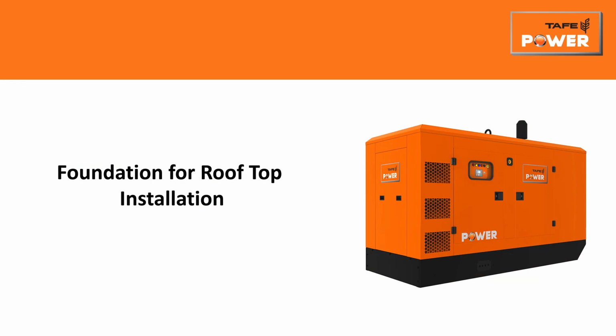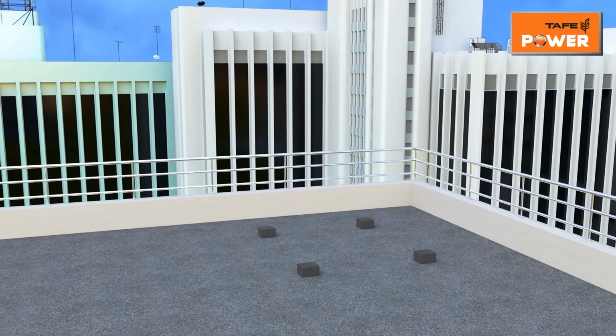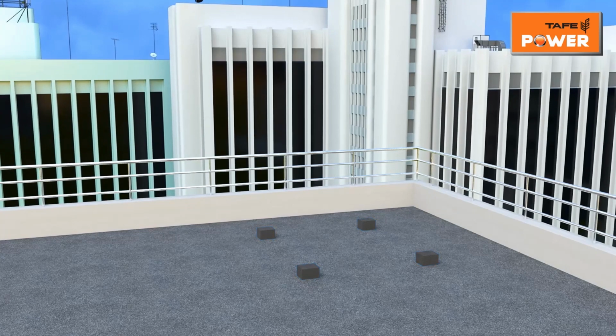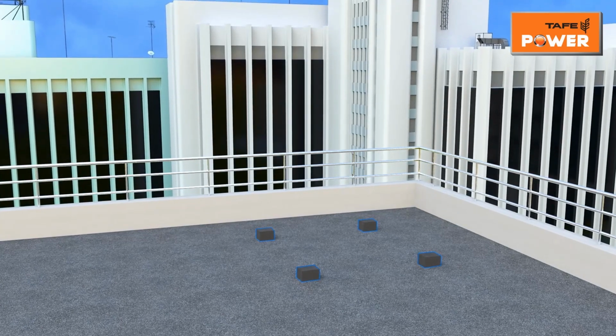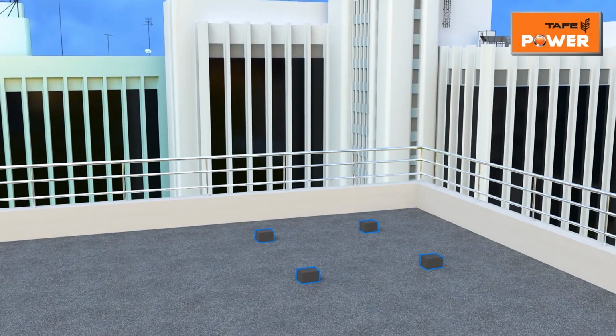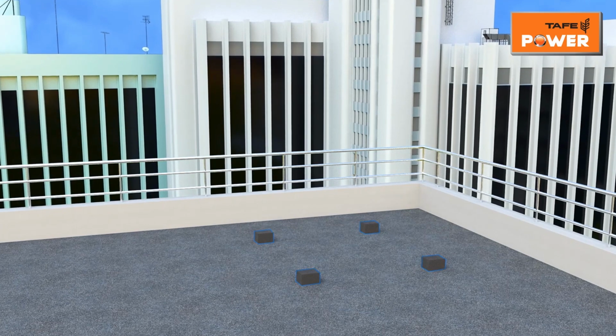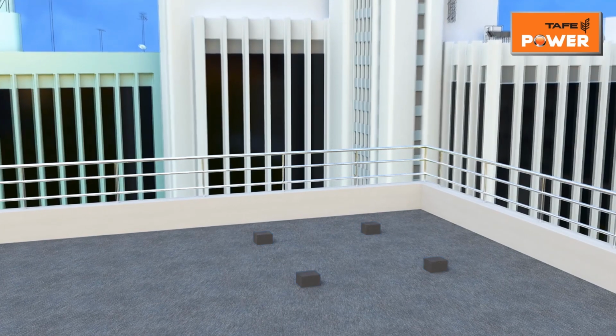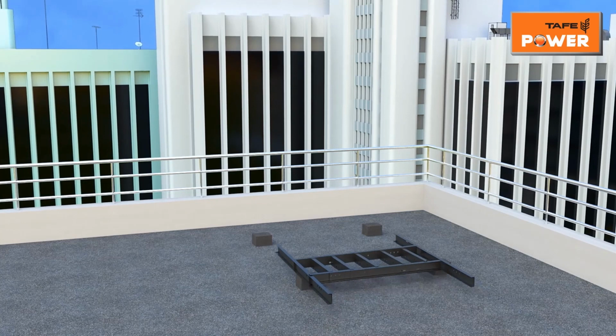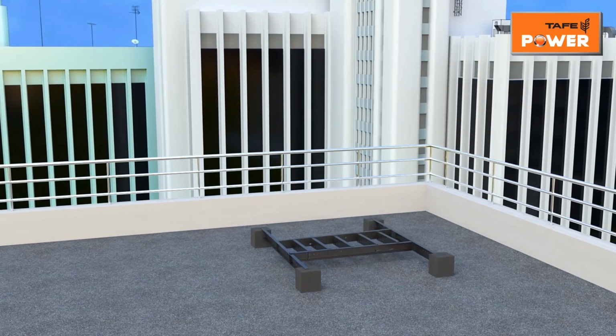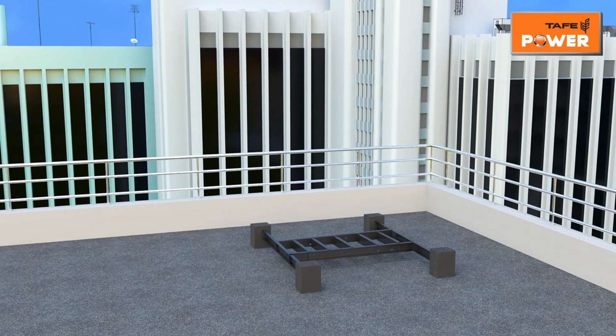Foundation for rooftop installation. A rooftop installation requires proper planning and the structural design considerations for dynamic loading. The weight of the genset should be on column and beam through proper foundation. MS channel should be used on the column of the building to cater the load of genset. MS sheet is already provided with TAFE power genset at the bottom of canopy, making it suitable for rooftop installation.